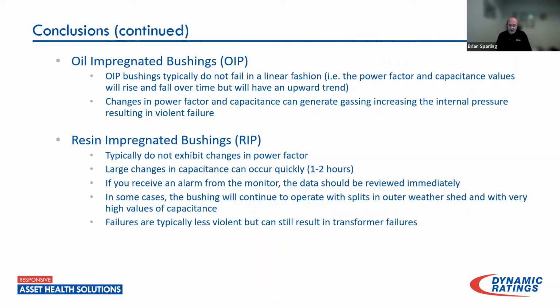And OIP bushings generally do not fail in a linear fashion. In other words, the power factor and capacitance values rise and fall over time, but will show a gradual upward trend over time. Changes in this power factor and capacitance can generate gassing, increasing the internal pressure and resulting in a violent failure. Whereas RIP type bushings do not typically exhibit changes in power factor because there is no oil, so there is no chance for moisture to begin to impact the insulation system whatsoever. So the thing we're looking for in RIP type bushings is large changes in capacitance. And these, as you can see in the data there, can occur quickly, over the space of 1 to 2 hours.